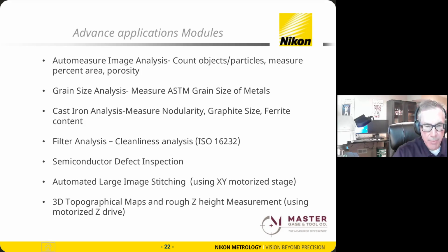And then using our Z drive, either for a single field of view or through a stitched field of view that maybe has some Z stacks collected, we can create 3D topographical maps and get some real rough Z height measurements. This is not like a profilometer or confocal type Z height measurement, but because our Z drive keeps track of the different focal points at different Z heights, we can get some rough Z measurements.